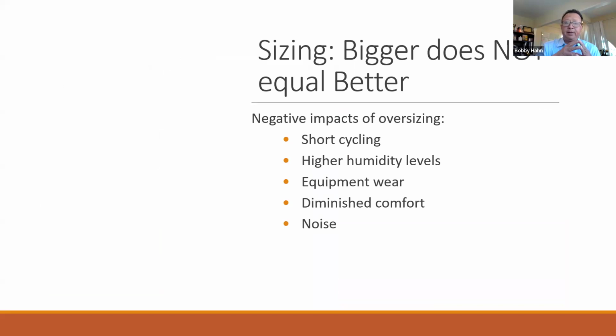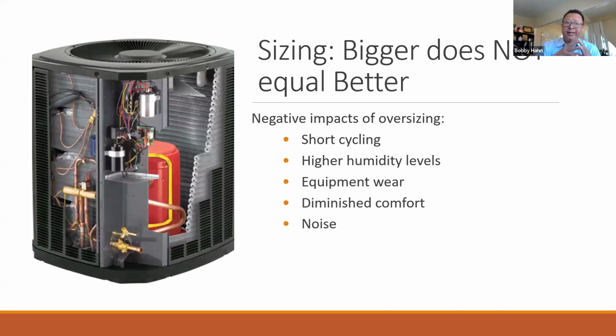And does bigger mean it's better? No, that's not true at all. If you oversize, that used to be the case. When there was any question, it was always make it bigger, because if it's too small, it'll never keep up. So short cycling's a huge one. If you oversize an application, the compressor is just going to flash on and off from high to low in a variable capacity heat pump. It's just going to be moving all the time. So cycling is not good.